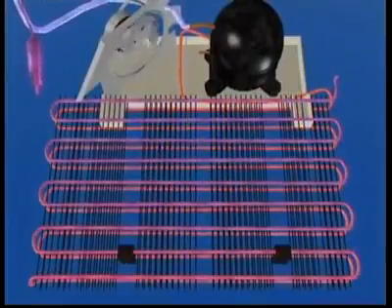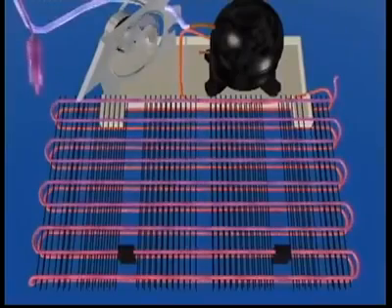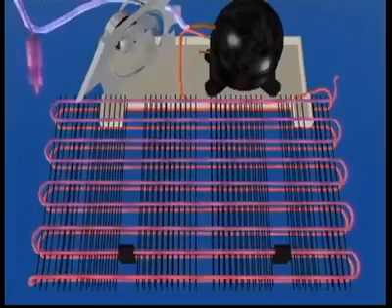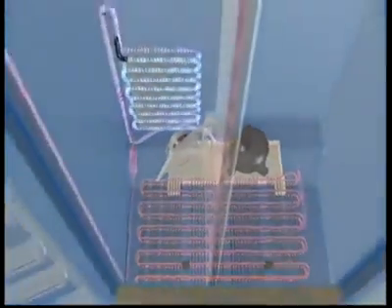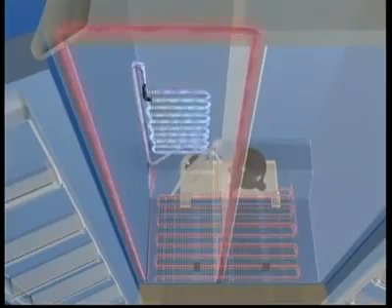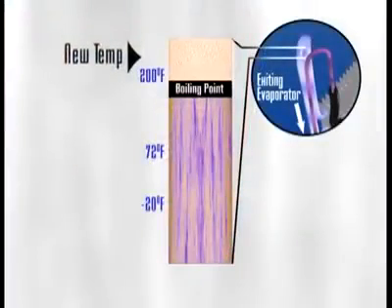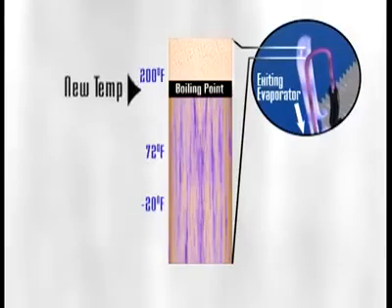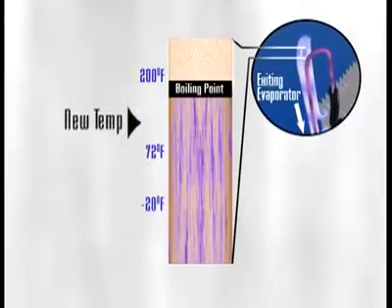As hot refrigerant travels through the condenser tubing, the cooler room temperature air around it absorbs some of the heat from it. Refrigerant exits the condenser still warm. We use that to our advantage and run a loop around the cabinet opening, where it will gently warm the surface, preventing any moisture and mold buildup. By the time the high-pressure gas reaches the end of the post-loop condenser, it has cooled to approximately 100 degrees Fahrenheit, passing below the new boiling point that we created, and thus changing from a gas back to a liquid.